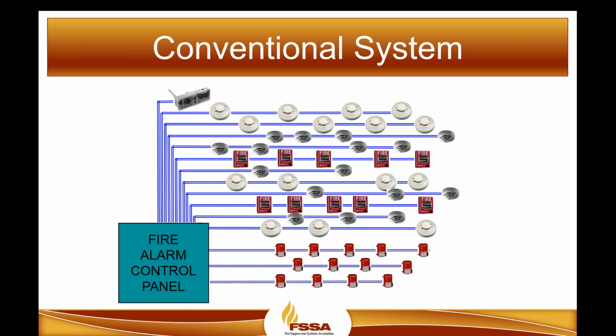so you really have to do your calcs on your audible circuits. Typically, the initiating is a Style B or Class B initiating device circuit to a Style D or a Class A, whether it's built on the boards or accessory boards can be added to these conventional systems to make it Class A. NACs are typically Style Y or Class B, or they can be Style Z or Class A for outputs, with onboard terminals or additional Class A boards that can be added after.